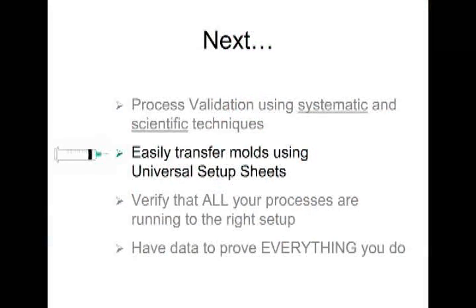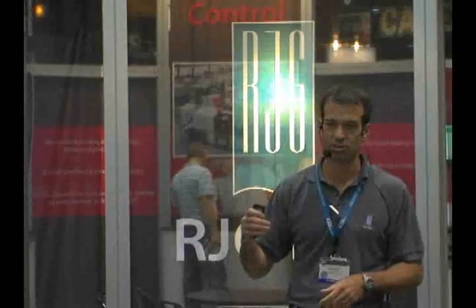We moved through that material pretty quickly, but hopefully you understand how a scientific, data-based approach using the four plastics variables can be utilized in the validation process. Now, another common problem for medical device molders is that once they've validated a process, they're locked into a machine. The reason that is typically the case is that the validation was done on machine-dependent variables as opposed to plastic-dependent variables. We're going to look at a couple of examples of those areas where process transfer is typically hung up.